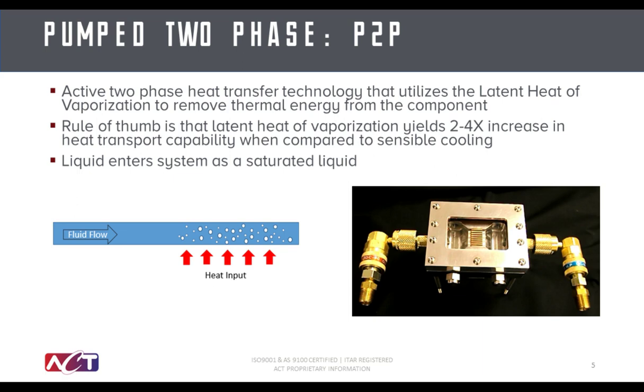Pump two-phase cooling is, as the name suggests, a two-phase cooling approach. It utilizes a working fluid that boils as it picks up heat from the heated components. We utilize the latent heat of vaporization to absorb much more energy than you could with the sensible heating of a liquid. Typically, this results in 2 to 4 times the amount of heat transport capability as compared to sensible cooling approaches like water glycol systems.